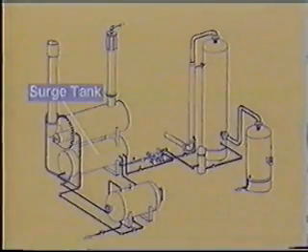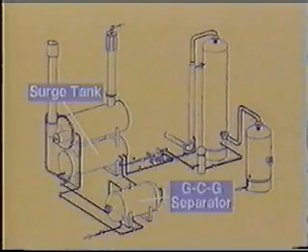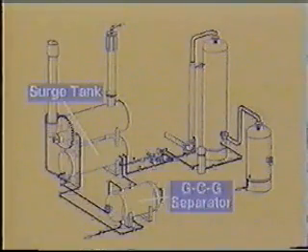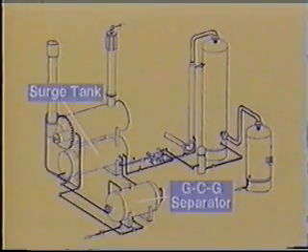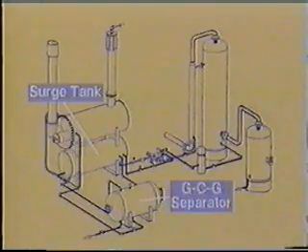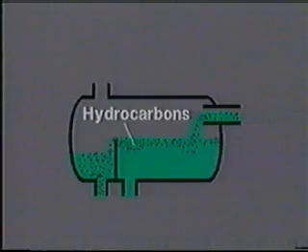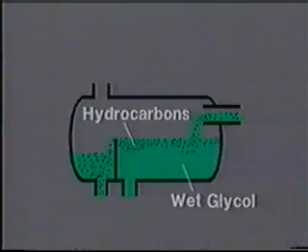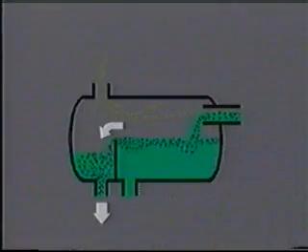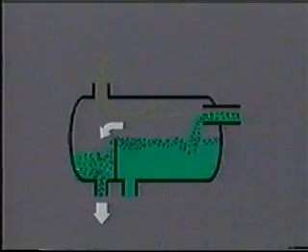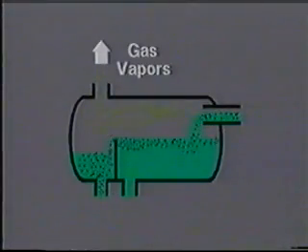After leaving the coils in the surge tank, the wet glycol enters the gas condensate glycol separator. The purpose of this vessel is to remove the gas and condensate hydrocarbons that were accumulated by the glycol on its path through the contactor. Heat causes the hydrocarbons to separate from the wet glycol solution; the hydrocarbon condensate is skimmed off and disposed of, and any remaining gas vapors exit at the top.